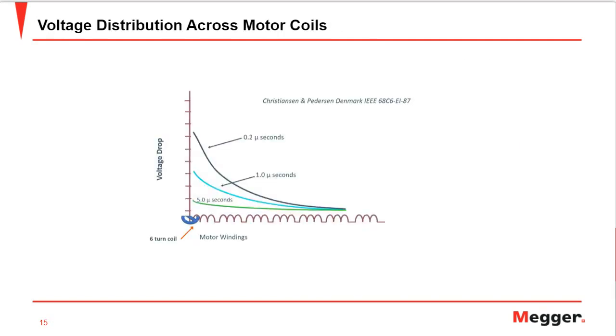There are various different factors for voltage spikes. One of them could be lightning, which is around 1.2 microseconds and falls near here on this graph. VFD switching is around 0.5 microseconds, which falls somewhere near here. As per an IEEE standard, which calls for a 0.2 microsecond rise, the test equipment which we are using to test the motor should be able to handle this 0.2 microsecond rise.